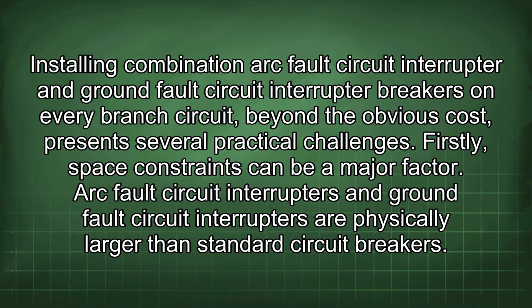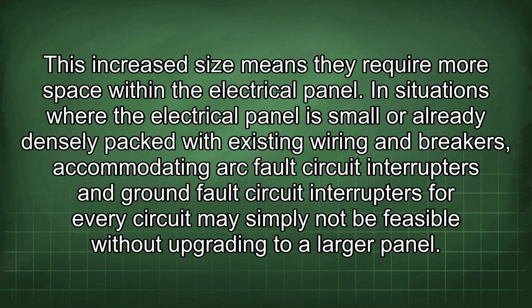Installing combination arc fault circuit interrupter and ground fault circuit interrupter breakers on every branch circuit, beyond the obvious cost, presents several practical challenges. Firstly, space constraints can be a major factor. Arc fault circuit interrupters and ground fault circuit interrupters are physically larger than standard circuit breakers. This increased size means they require more space within the electrical panel.